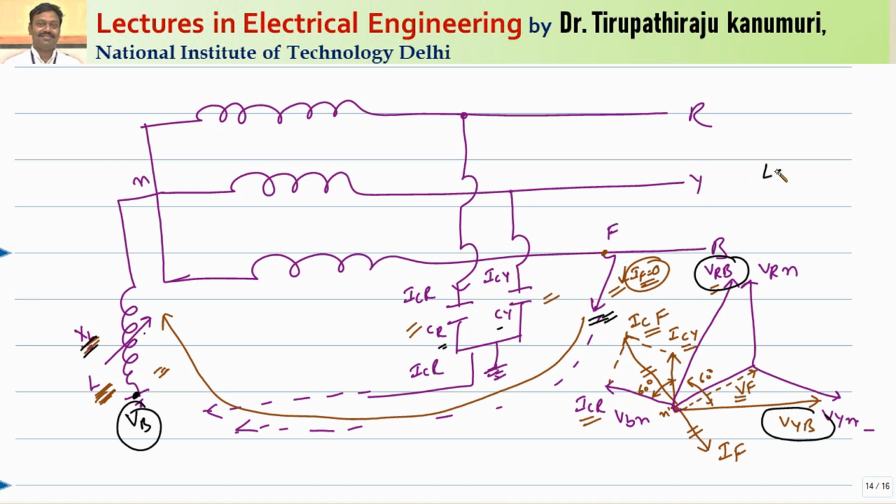So now if you want to disconnect this fault after some time, because practically what happens, most of the cases this line to ground faults happens either because of the lightning, or during some trees will come and fall on your line. So because of that also it can happen. And the third reason is because of the birds. So in all these cases, the fault will get disconnected by itself within few seconds or within few minutes in 70 to 80% of the cases.